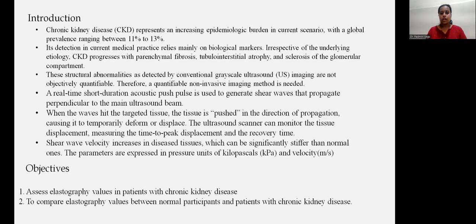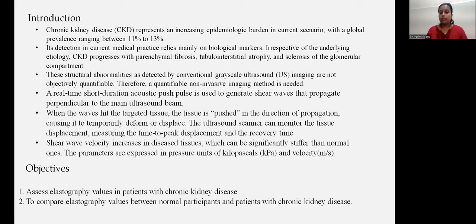A real-time short-duration acoustic push pulse is used to generate a shear wave that propagates perpendicular to the main ultrasound beam. When the waves hit the targeted tissue, the tissue is pushed in the direction of propagation, causing it to temporarily deform and displace. The ultrasound scanner can monitor the tissue displacement, measuring the time to peak displacement and the recovery time. Shear wave velocity increases in diseased tissues, which can be significantly stiffer than normal ones. The parameters are expressed in pressure units of kilopascals and velocity in meters per second.